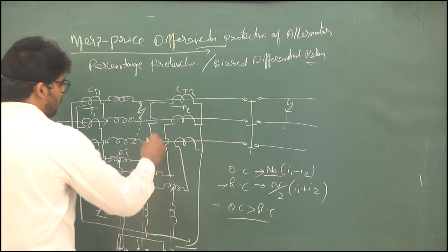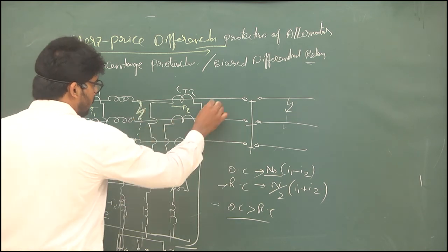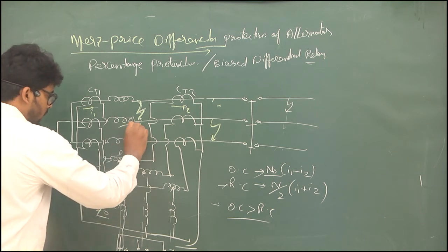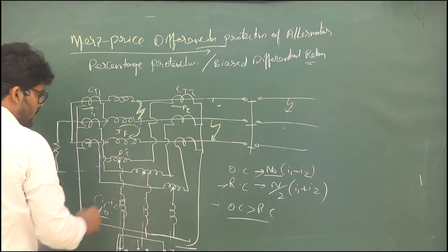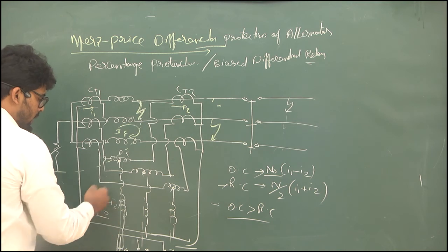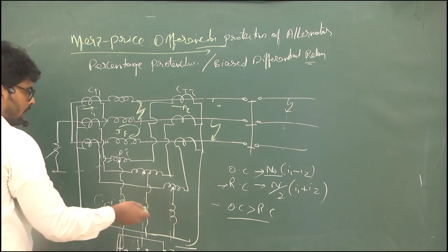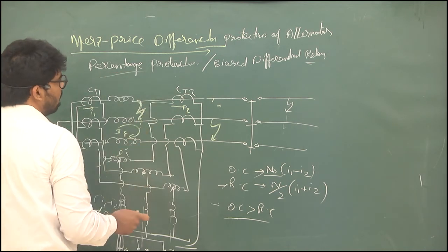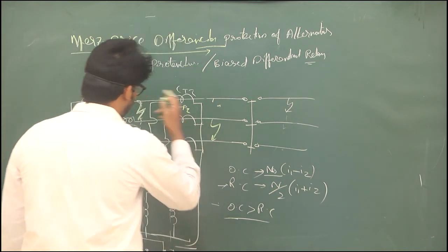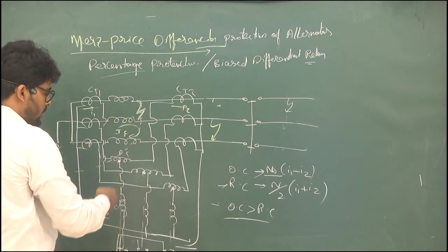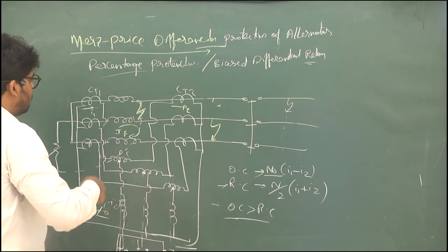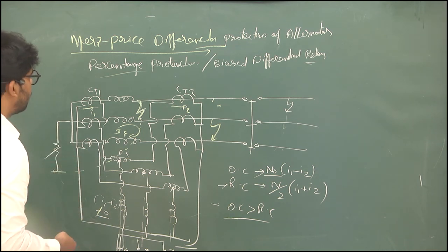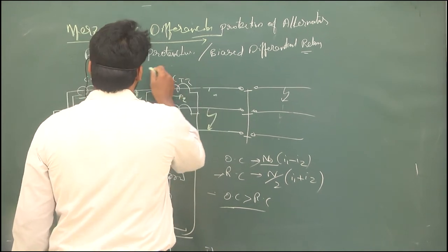Likewise, if a fault occurs internally, say this is a phase to phase fault, an internal current flows through this. If this internal current flows, again there is a difference between I1 and I2, and the coil will operate. So this percentage Merz-Price protection relay will operate for internal phase to ground and phase to phase faults. This is the operation of Merz-Price differential protection, the percentage protection.